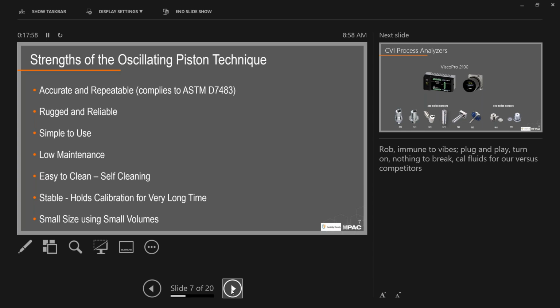About the stability, how long do these hold calibration? How long do they need to be recalibrated? We found that the sensors, we pulled them out of lines after 10 years, and they are still within their 1% application accuracy specification. However, we do need to recommend some type of calibration check, and we have, because our customers request that, so we suggest doing that on an annual basis. So it's a very simple procedure to do a calibration verification of the instrument. And again, the small sample volume and small size of the sensor makes it a very beneficial system.